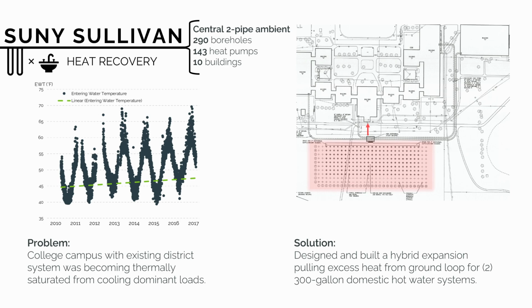Part of the reason this was happening is that it was already a hybrid system, because there was a propane boiler in building H, the long skinny one in the top right, which was handling a lot of the outside air heating loads as well as some perimeter heating loads.